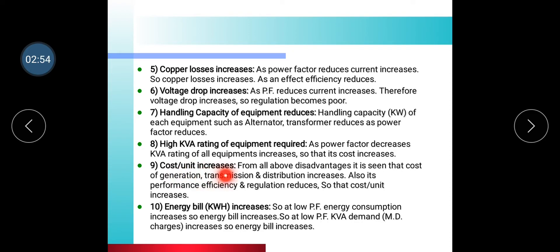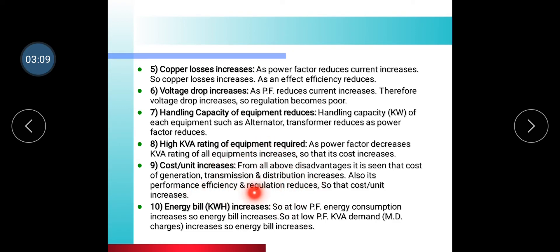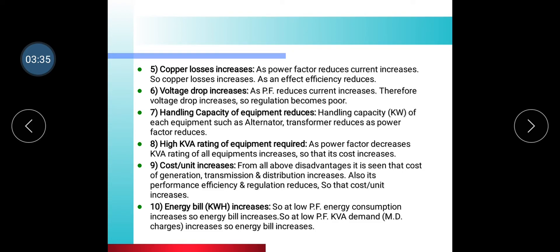Cost per unit increases. From all the above disadvantages, it is seen that the cost of generation, transmission, and distribution increases, while performance, efficiency, and regulation reduce. Additionally, at low power factor, kVA demand increases, energy consumption increases, and therefore the energy bill increases.